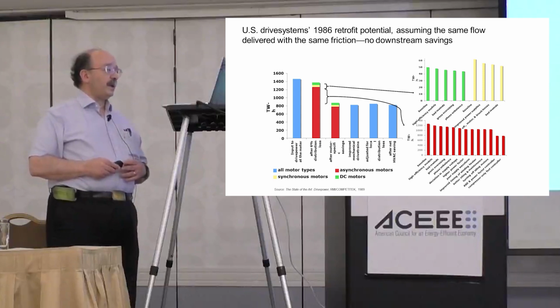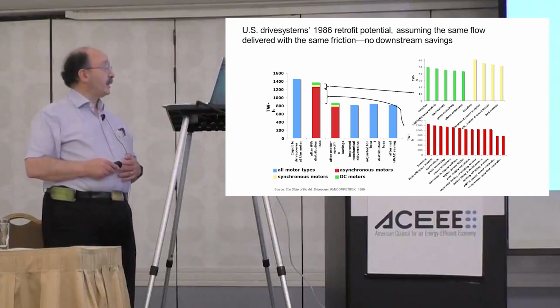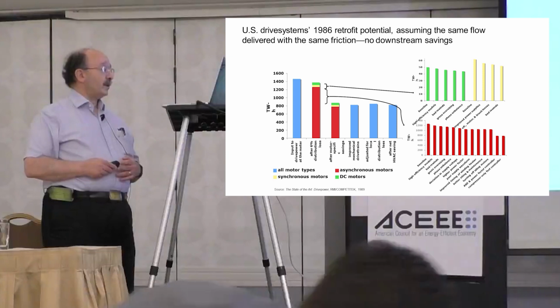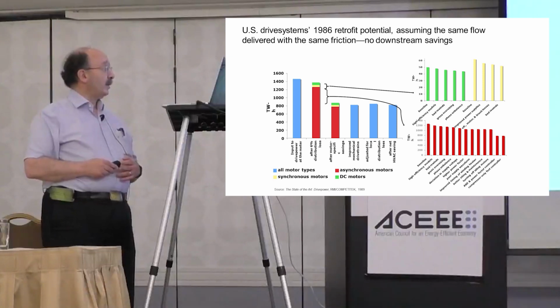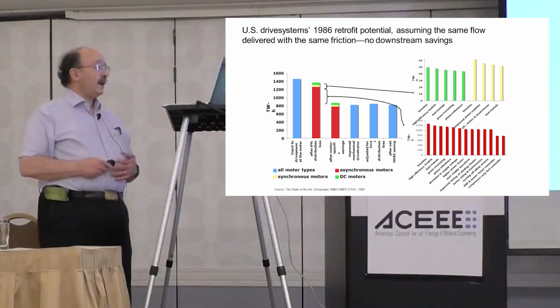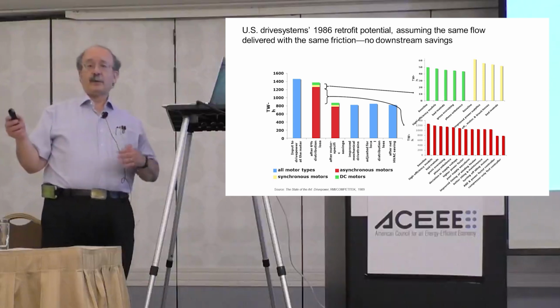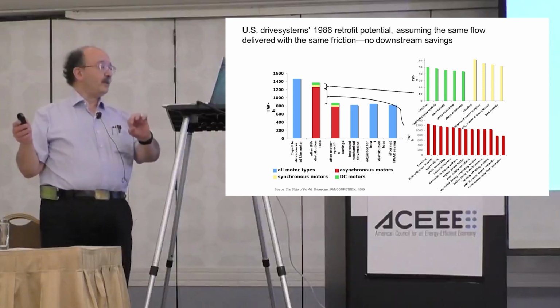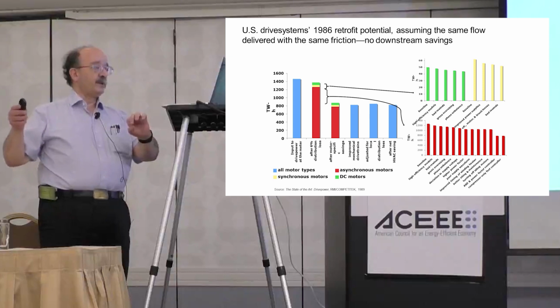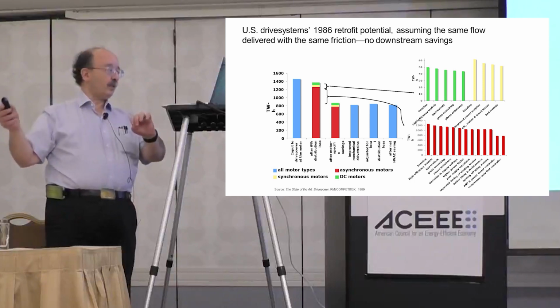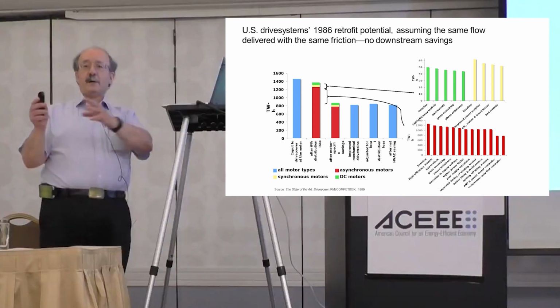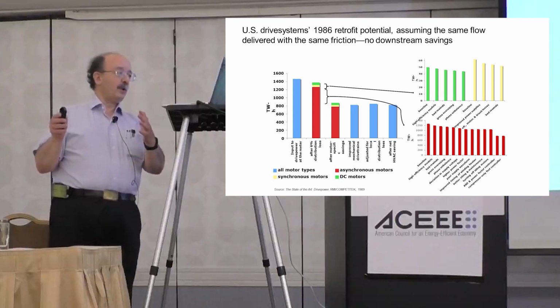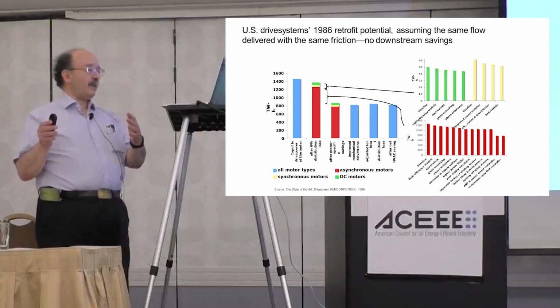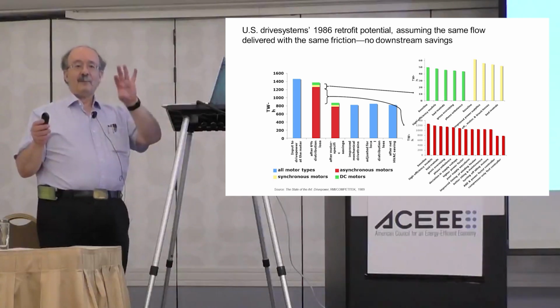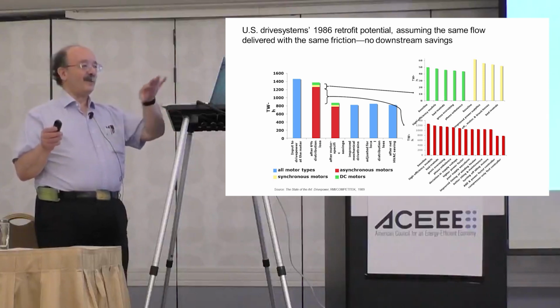Our 1989 systems analysis of this potential examined induction motors in red, synchronous in yellow, DC in green. Our system boundary was from the electric meter to the input shaft of the driven machine, so we counted efficiency upstream in the wires and controls, in the motor itself, and in the mechanical torque transmission to the load, but we didn't count the pumps, pipes, valves, etc.